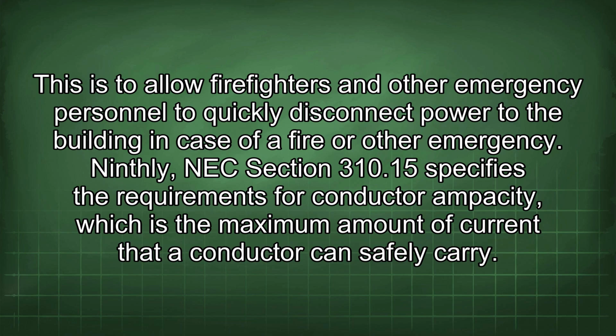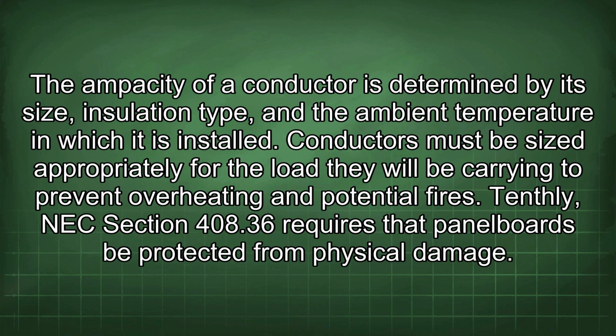Ninthly, NEC Section 310.15 specifies the requirements for conductor ampacity, which is the maximum amount of current that a conductor can safely carry. The ampacity of a conductor is determined by its size, insulation type, and the ambient temperature in which it is installed. Conductors must be sized appropriately for the load they will be carrying to prevent overheating and potential fires.